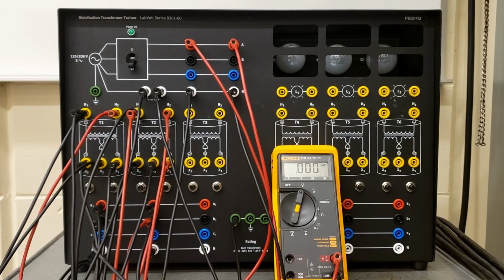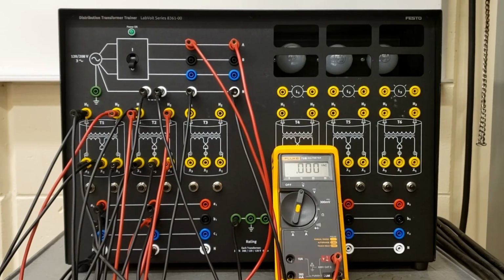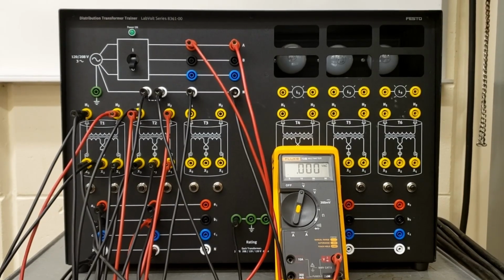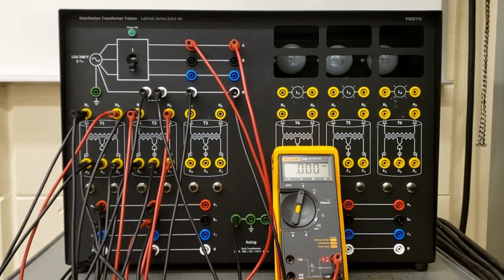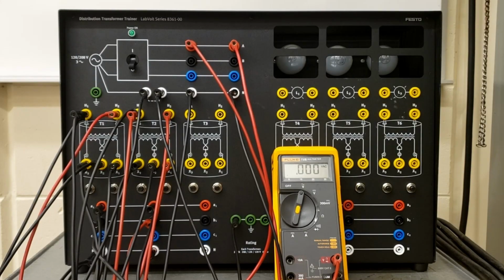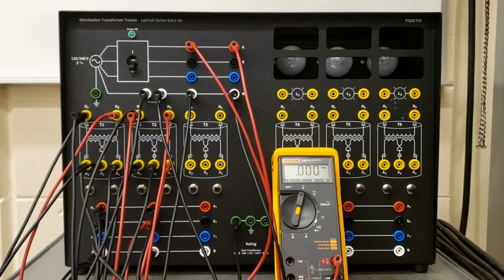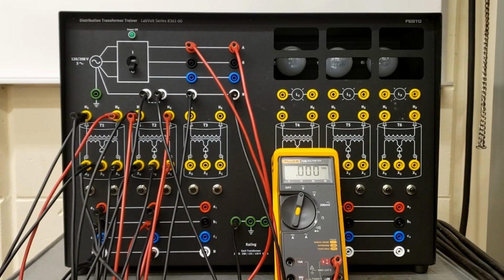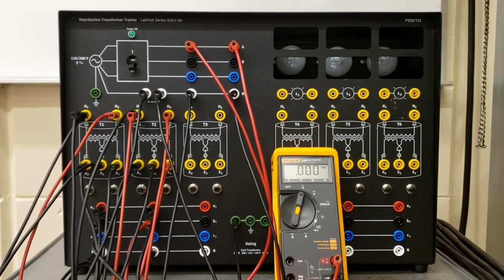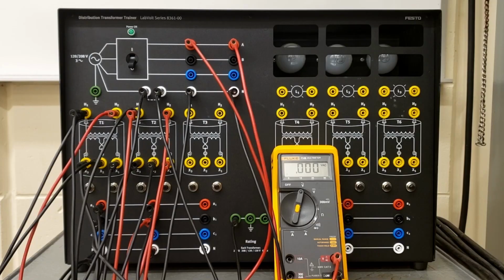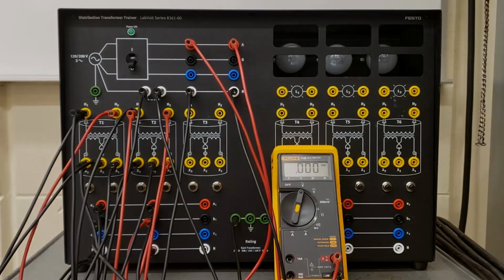The next one, on page 7 of the student manual and page 8 of the instructor manual, is the delta to delta, 0 degree phase shift connection. So what I'll do is stop here, and we'll do a quick diagram going through that one they've given, then come back and connect it up, and take those voltage readings between A and B, B and C, and C and A - they should all be identical, at 240 volts.